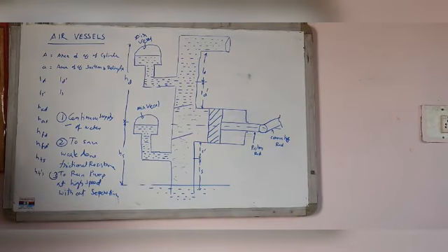During the second half of the delivery stroke, the piston moves with retardation, and the velocity of water in the delivery pipe will be less than the mean velocity. The water already stored in the air vessel will start flowing into the delivery pipe, and the velocity of flow in the delivery pipe beyond the point to which the air vessel is fitted will become equal to the mean velocity.